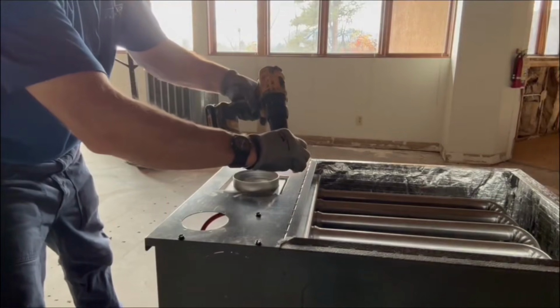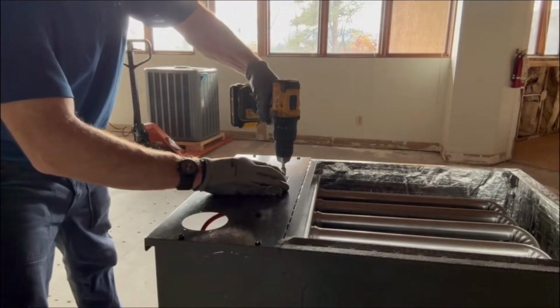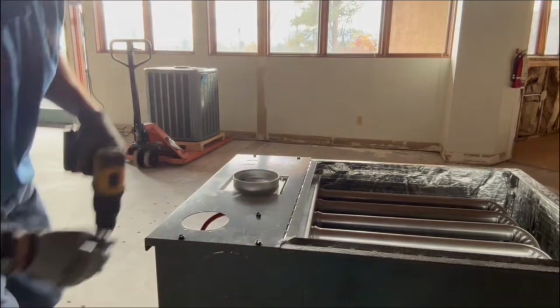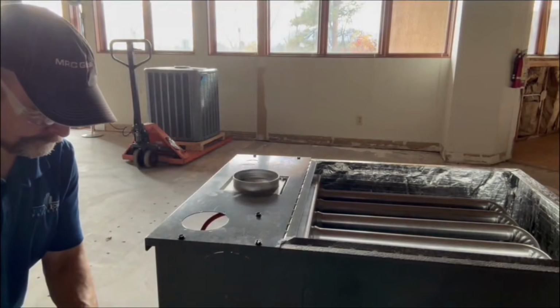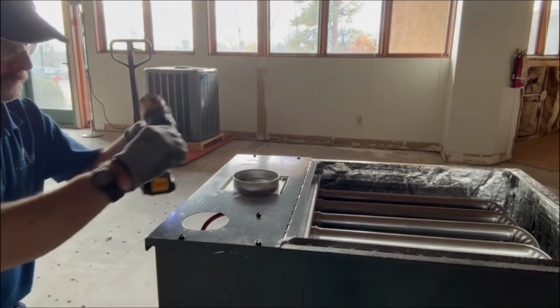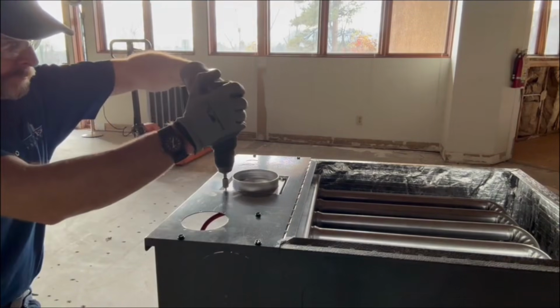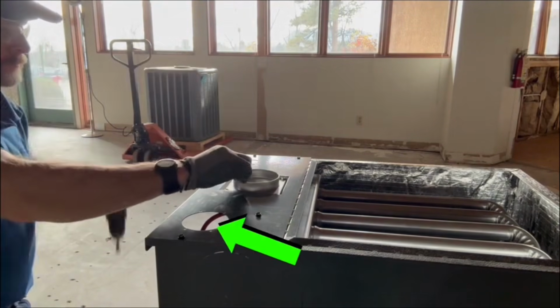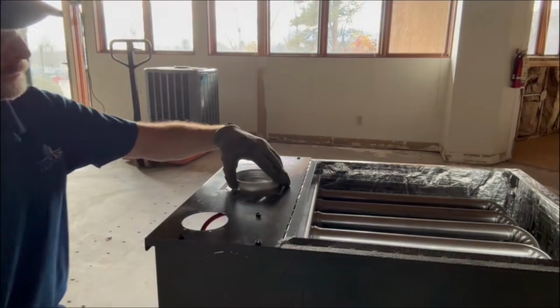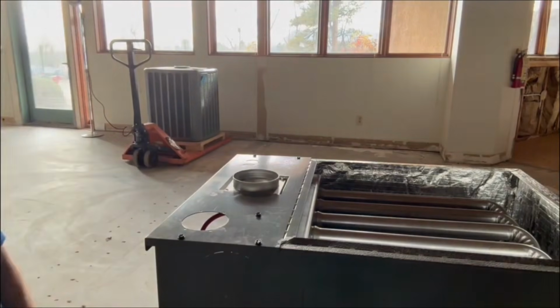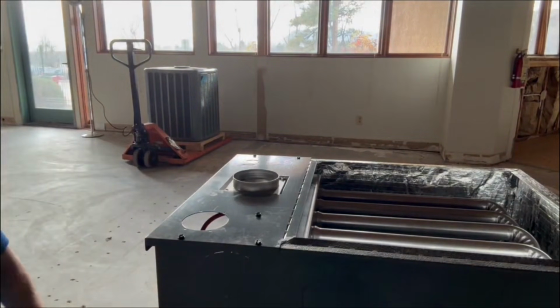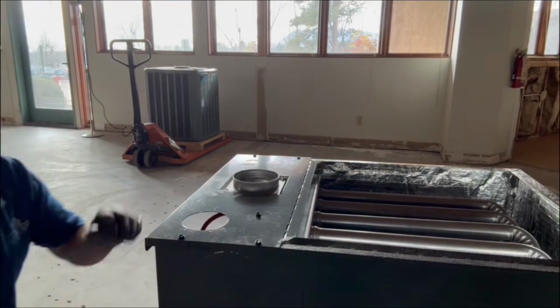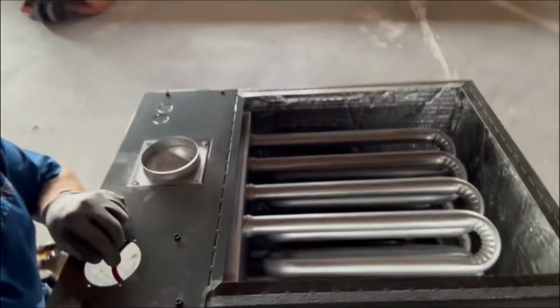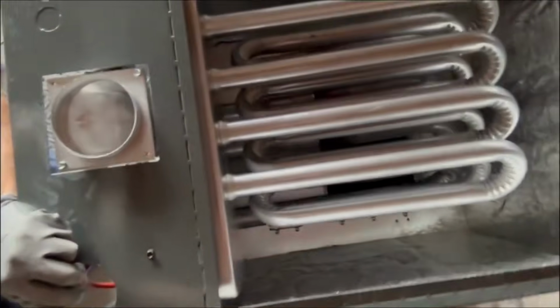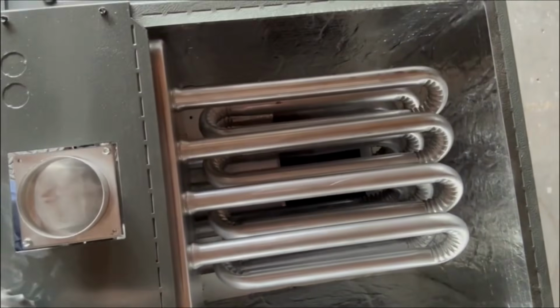Because this is an A2L R32 system, you notice there's no louvers anywhere on the front or side of the cabinet. The way it brings fresh air in, combustion air, is through this opening here. So per the instructions, I'll have to install a PVC pipe and an elbow or a U-bend to bring fresh air into the combustion chamber. A better view. Here's your heat exchanger, blower motor down below the heat exchanger.